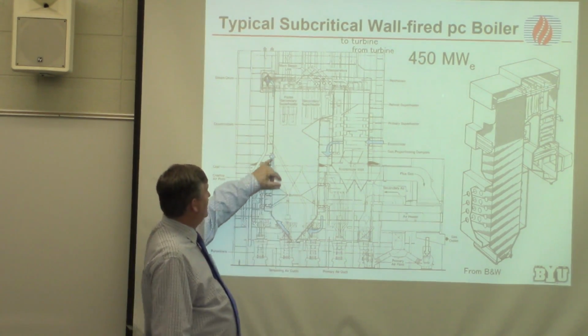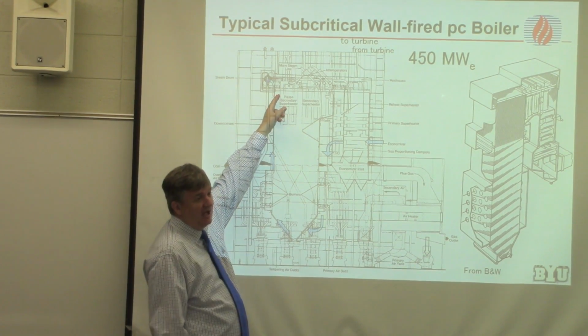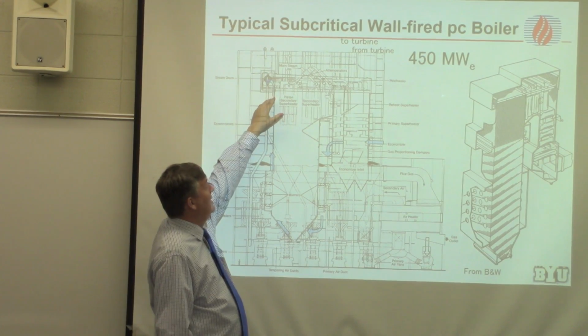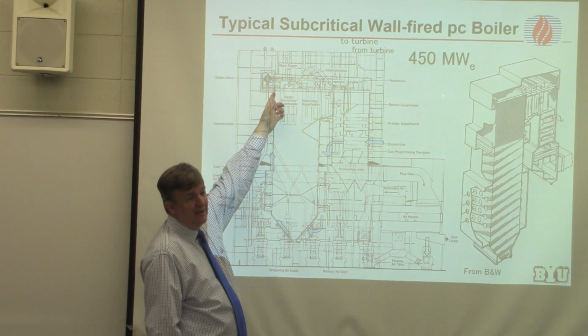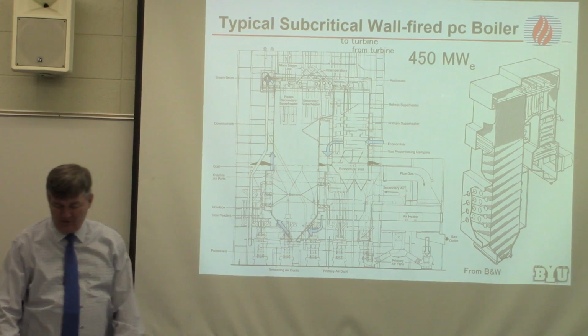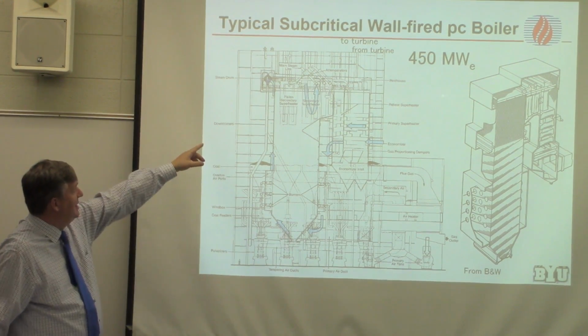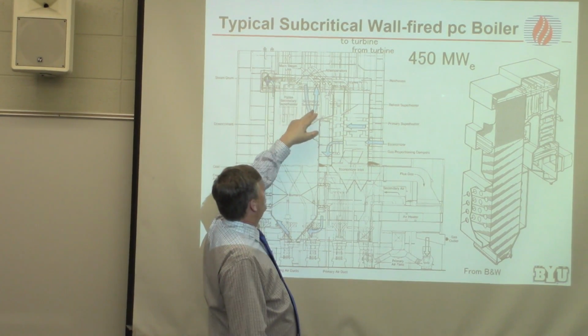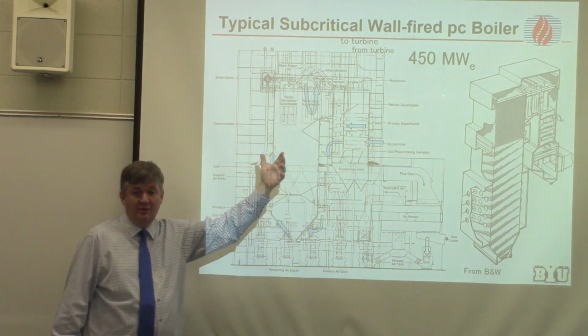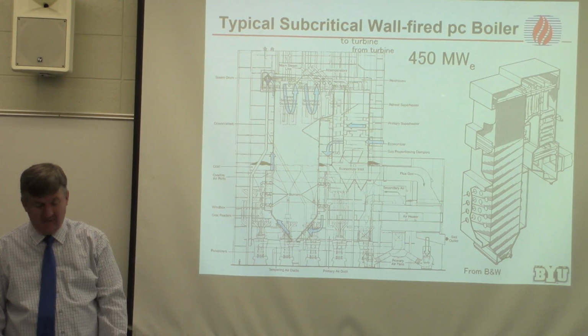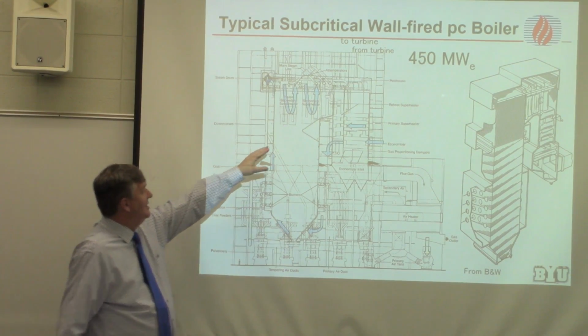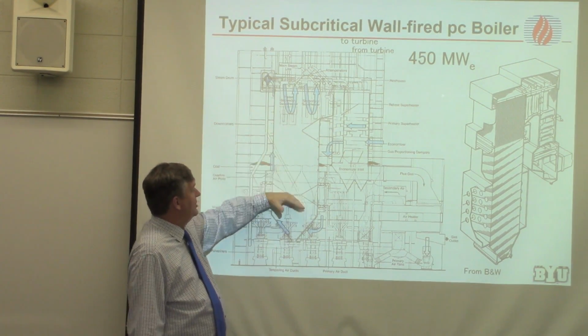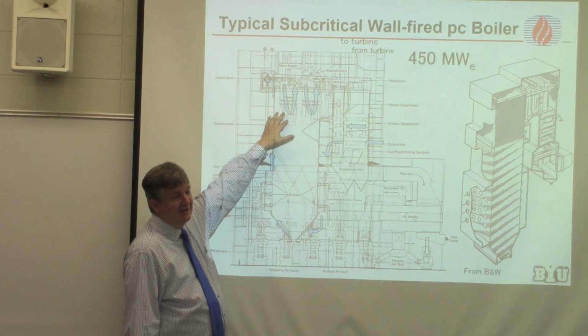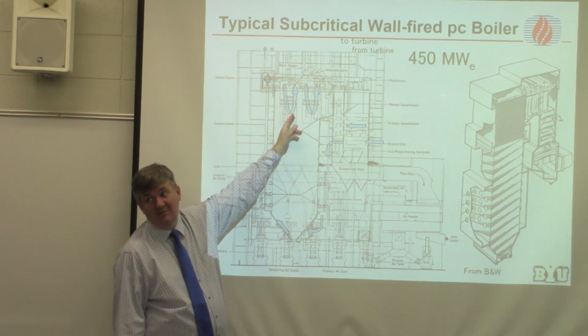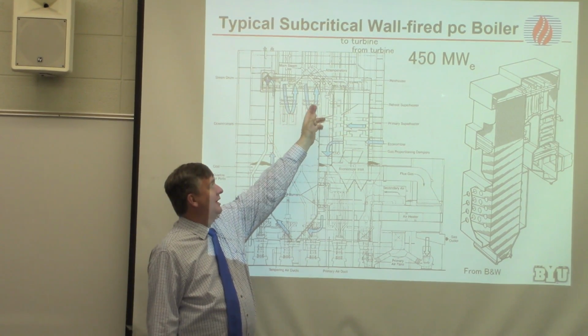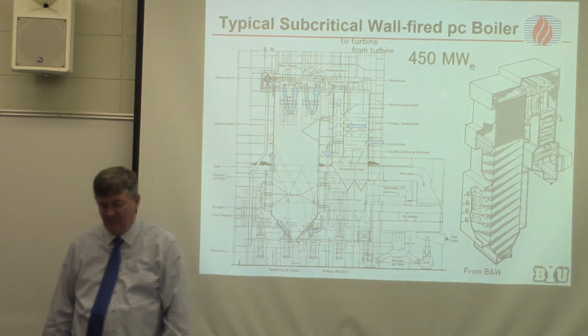And as it goes up here, it gets heated and heated, and it's usually designed so that by the time it gets to the top of the boiler, it's starting to form steam, saturated steam. Then it goes to a steam drum where it separates the water from the steam, and then the steam is injected through the superheaters to be superheated, so it's no longer saturated. Typically, even though this is low temperature compared to here, this is still a really hostile environment. So typically the first superheater it sees is not the hottest superheater, because they want to protect the metal that's at the hottest back here, usually at a little bit colder temperatures up there.